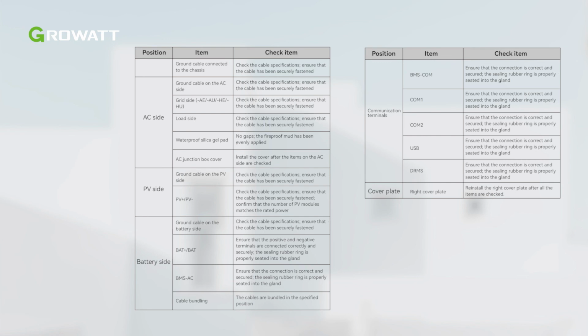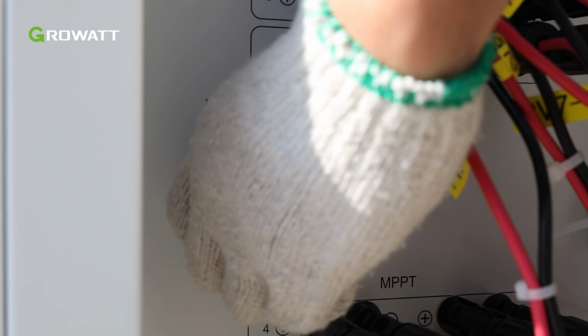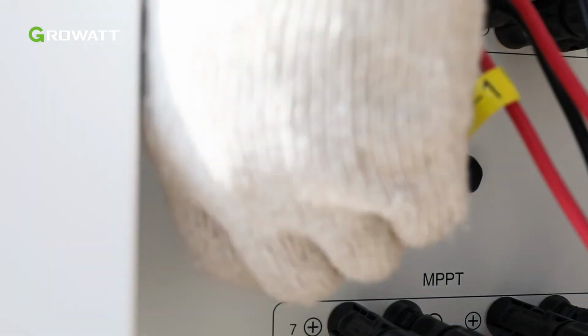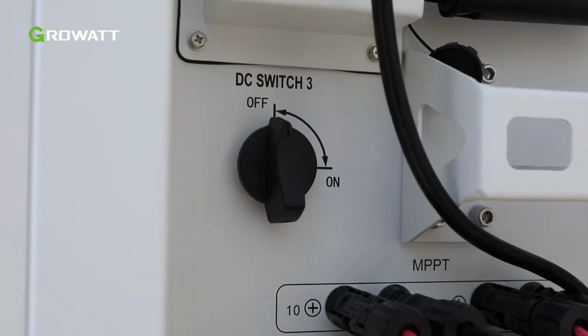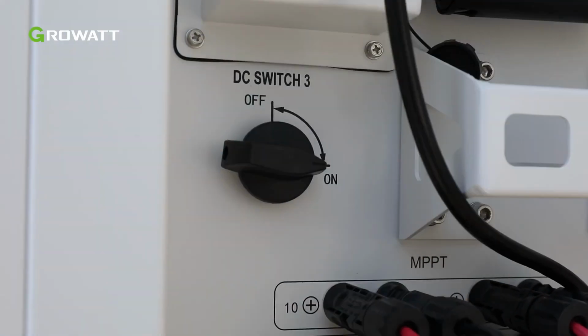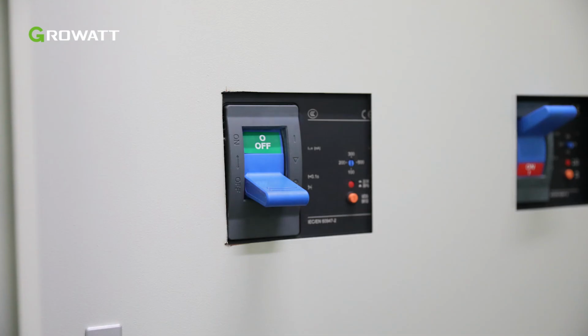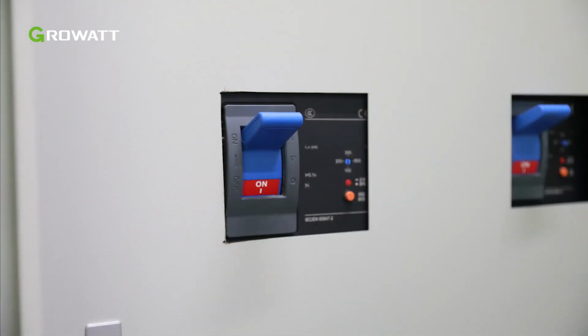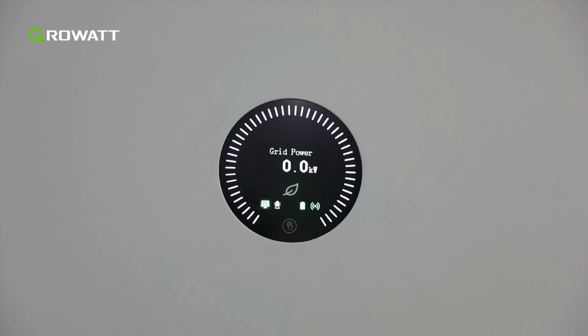After installation, please refer to the table in the user manual and check each item. Follow these steps to turn on the inverter. Turn the DC switches on the WIT inverter to the on position. Turn on the breaker between the grid and the inverter. Once the startup requirements of all terminals are fulfilled, the system will be powered on automatically.